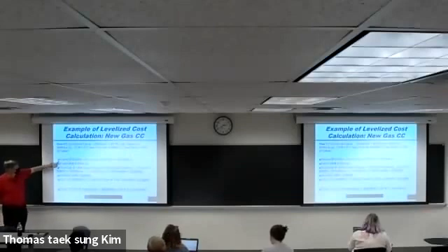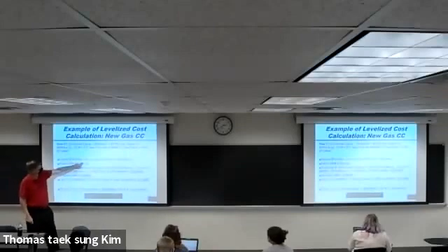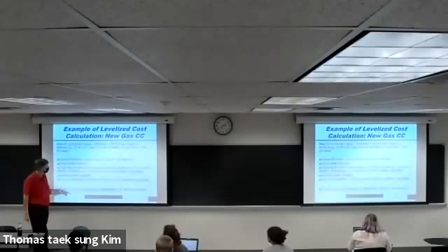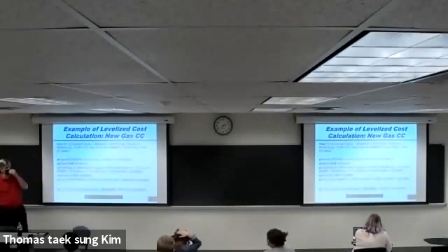Okay. So we're going to assume here a capital of $1,200 a kilowatt. So the annual capital is 1,200 times 0.1, so $120 per kilowatt year. The fixed O&M, we're assuming $30 a kilowatt year.